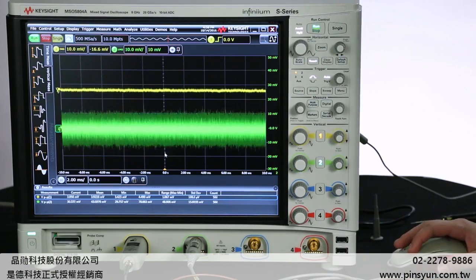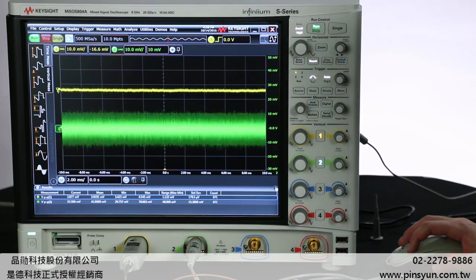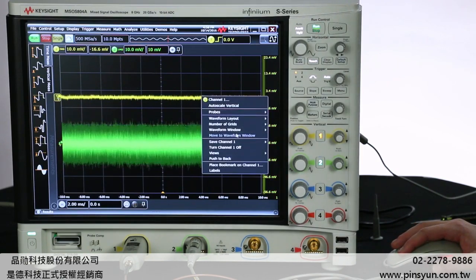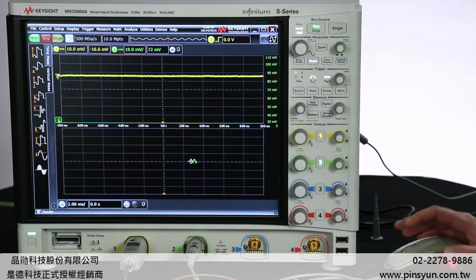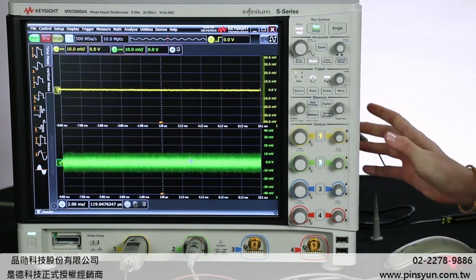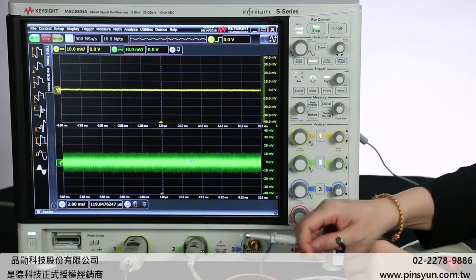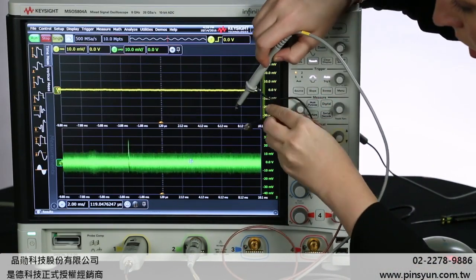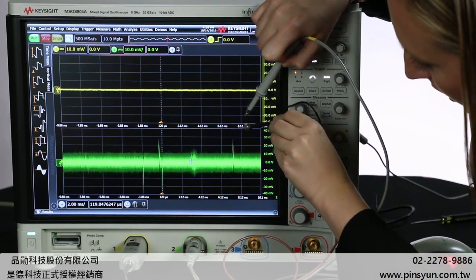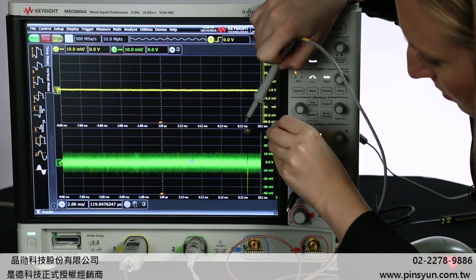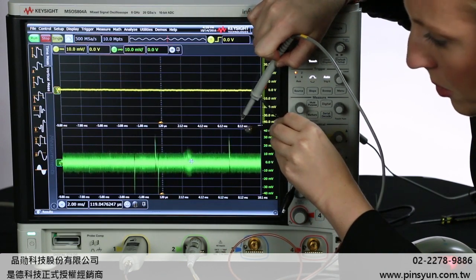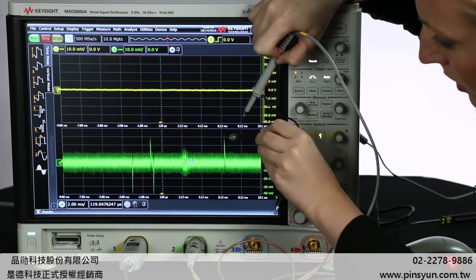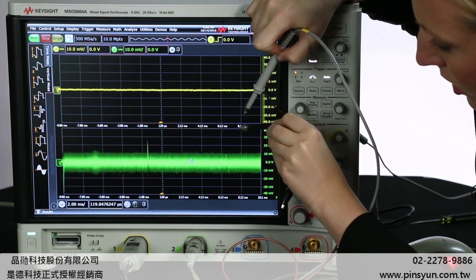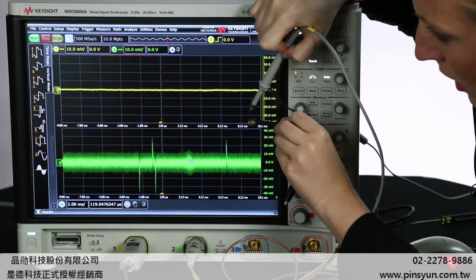Let's go ahead and take a closer look at this. Let's go ahead and expand our view. Let's separate these into grids. Center the waveforms, just so we can really get a good look at what's going on. And both of these probe tips are held up to the screen, and again, the passive probe is really picking up noise, whereas this active probe is just really not. It's not picking up any of that noise.